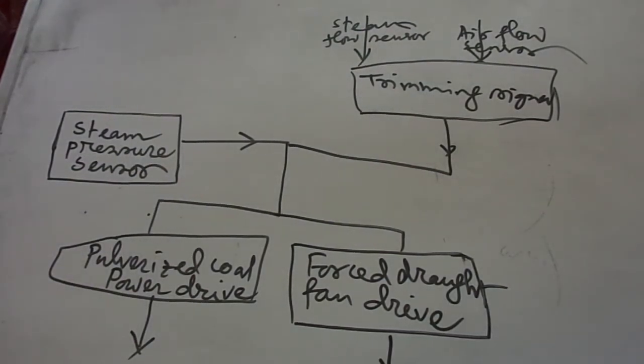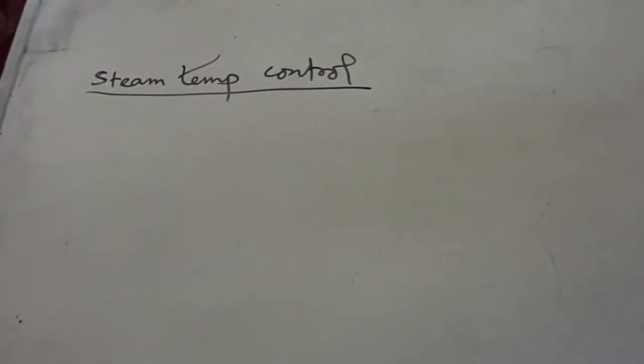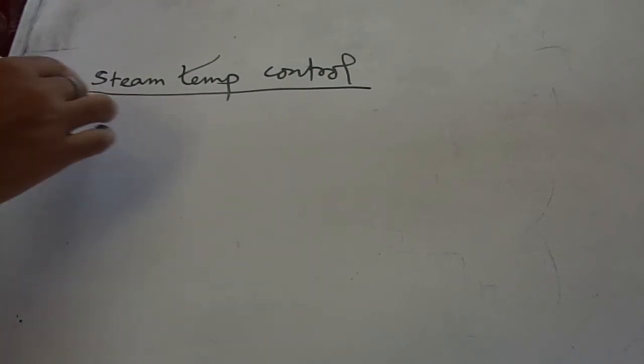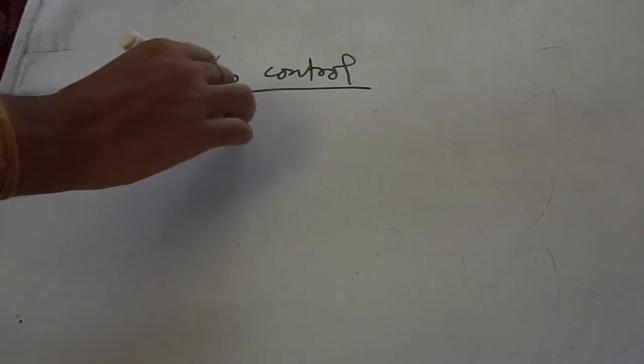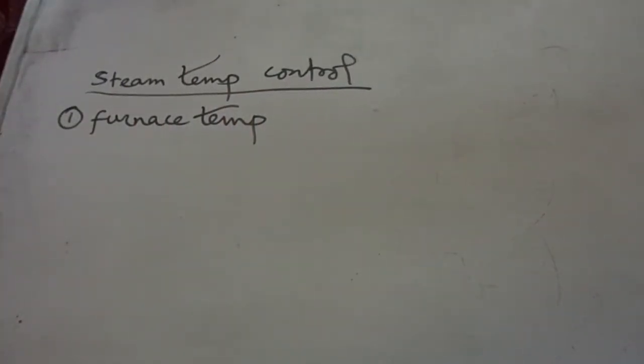Another one is the steam temperature control. An accurate control of superheat temperature is important for efficient power plant operation. The principal variables affecting superheat temperature are: first one is the furnace temperature.